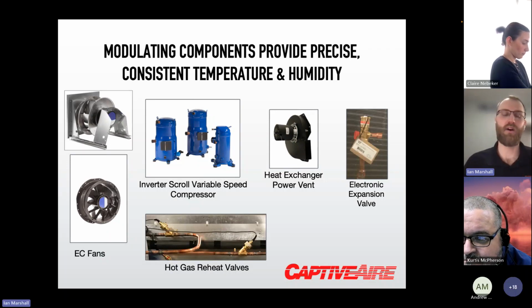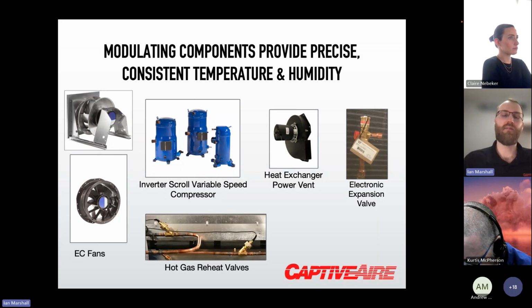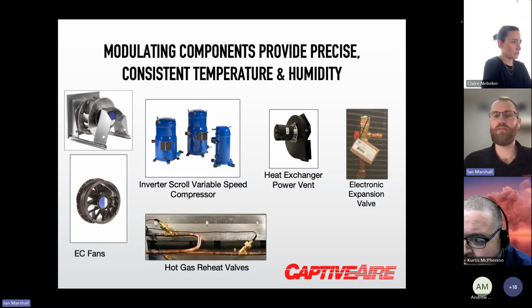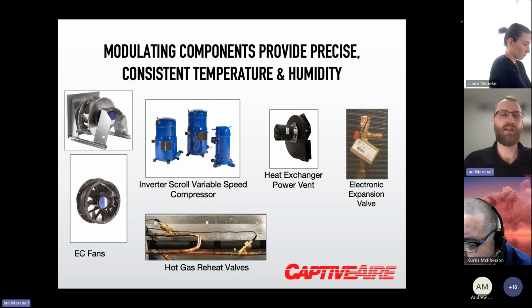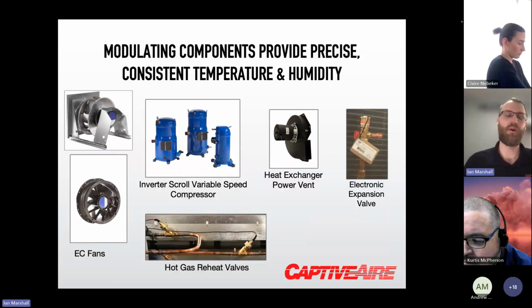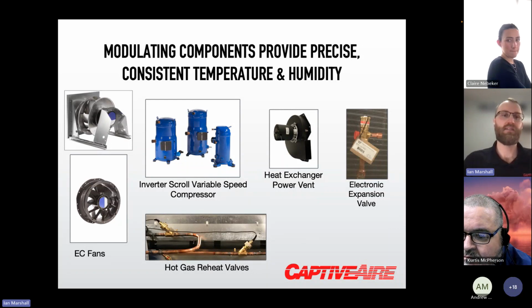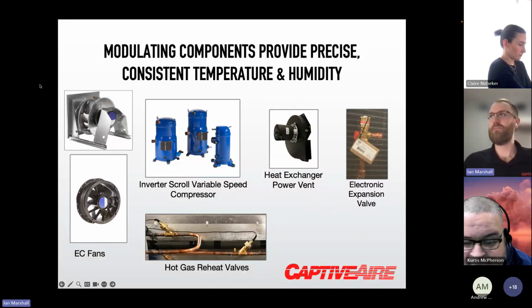As I mentioned, the compressor, it's all inverter scroll compressors. So it's true variable speed with a VFD tied to control the speed. All of our heating options are all fully modulating. So whether it's indirect fired or electric or heat pump, all variable speed. We use an electronic expansion valve, not a thermal expansion valve. Our condensing fans are ECM fans standard. And we use a fully modulating hot gas reheat. So just to name a few of the components, again, we don't offer fixed staged components or staged heat options. It's all variable speed.